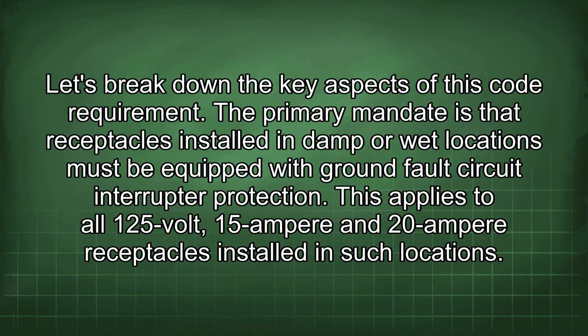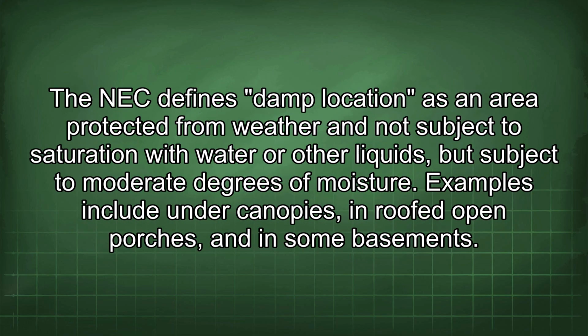The primary mandate is that receptacles installed in damp or wet locations must be equipped with ground fault circuit interrupter protection. This applies to all 125 volt, 15 ampere and 20 ampere receptacles installed in such locations. The NEC defines a damp location as an area protected from weather and not subject to saturation with water or other liquids but subject to moderate degrees of moisture. Examples include under canopies, in roofed open porches, and in some basements.